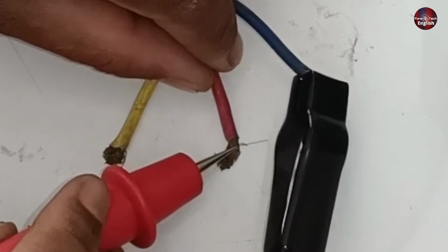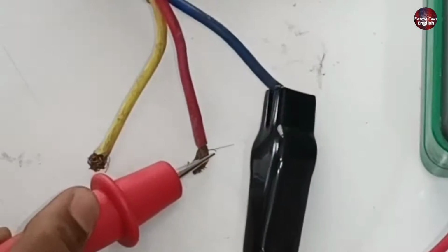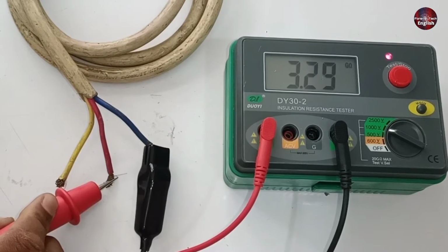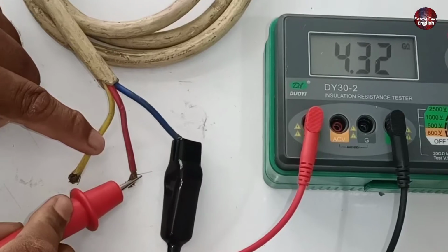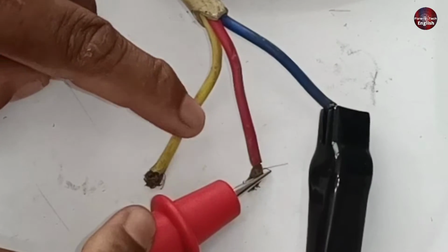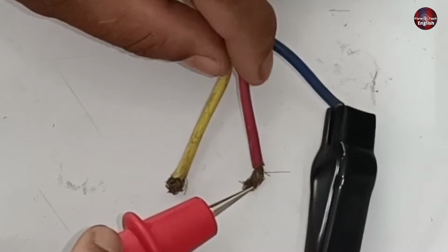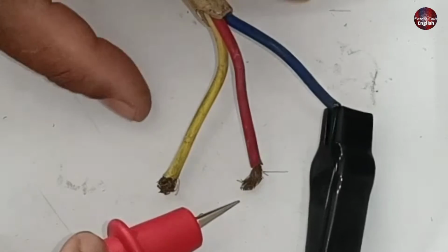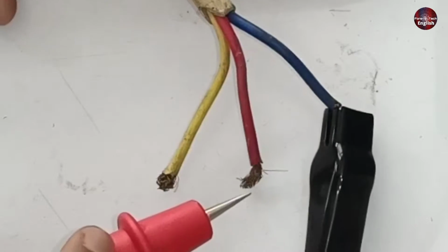The same, I have attached the probe with the red wire, and pressed the start button, and we got the same value. This means the blue wire is not internally attached to the yellow and red wire. And this is how we test insulation resistance for a wire.